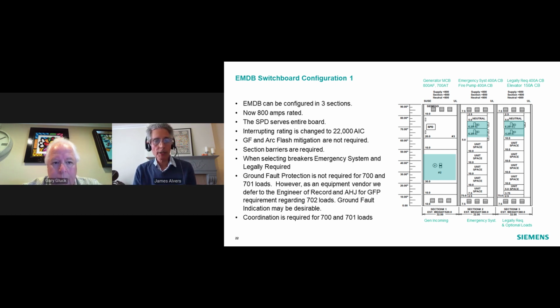The interrupting rating has been changed to 22,000 amps. This is going to save, obviously, money, but may save a bit of space as well, depending upon the configuration. Ground fault protection, as we mentioned, is not required for this board. Arc flash mitigation is not required because everything's under 1200 amps. Section barriers are required, and that's a good thing to put in your specification to make sure you get those section barriers.